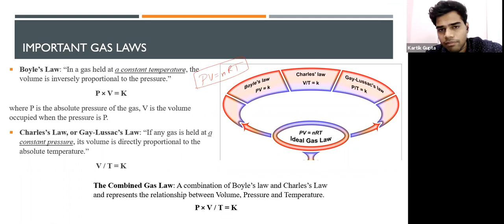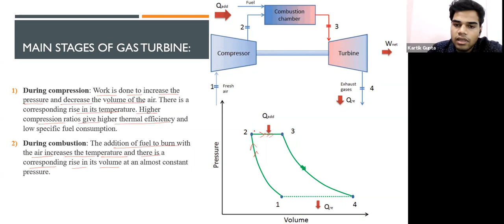So what are the main stages of the gas turbine? I just told you, but let's go in brief. During compression, work is done to increase the pressure and decrease the volume of the air. Pressure is increased, volume is reduced. Temperature is also increased. Higher compression ratios give higher thermal efficiency. That is why in the video you saw there were two sets of compressors, not only one. Because the higher the compression, the better the combustion. During combustion, we add fuel to burn with the air, increasing the temperature, and there is a corresponding rise in the volume. Pressure remains constant, volume increases.